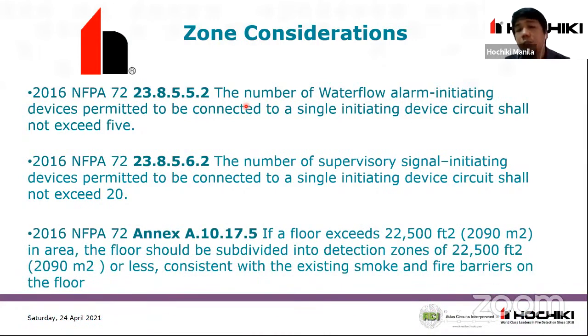Last, if a floor exceeds 22,500 square feet or 2,090 square meters in area, the floor should be subdivided into detection zones. So meaning lang nito, yung limitation natin ng isang zone, ang area of limitation is up to roughly 2,000 square meters. So kapag yung area natin is more than 2,000 square meters or 2,090 to be exact, kailangan mag-install na kayo ng panibagong zone. Okay?